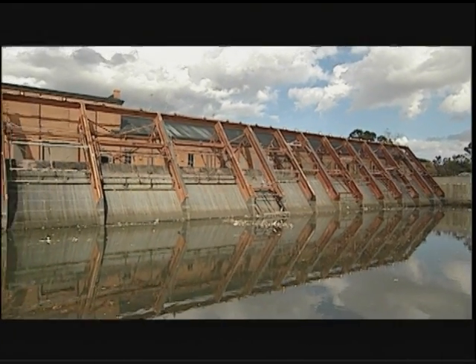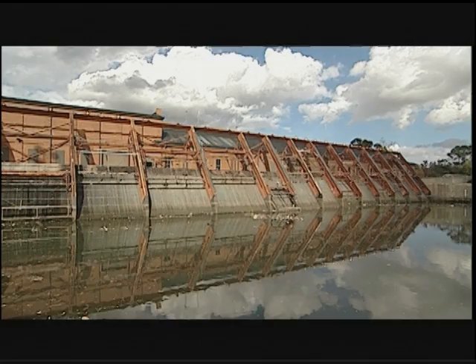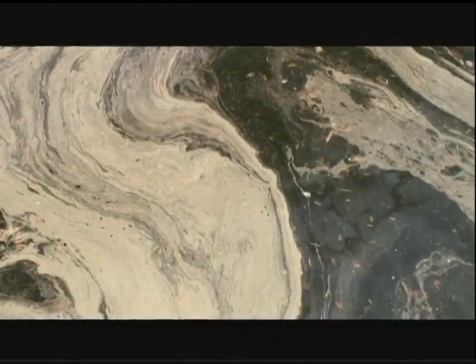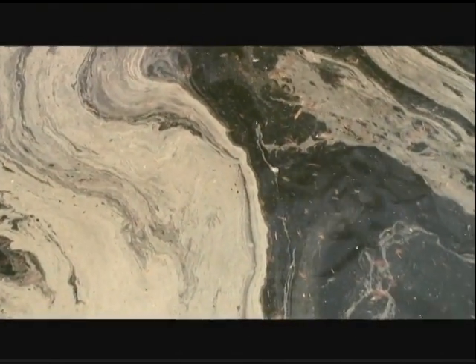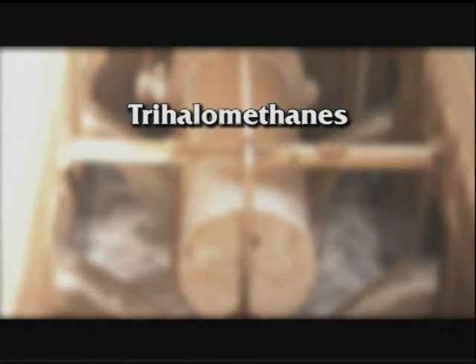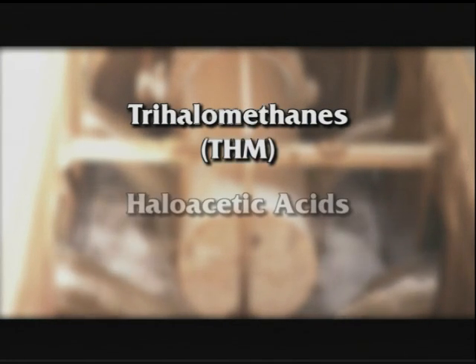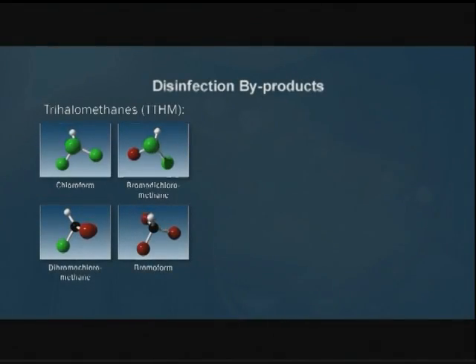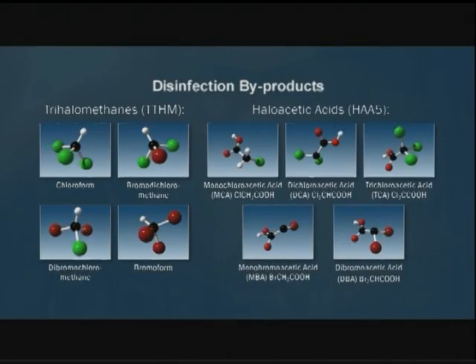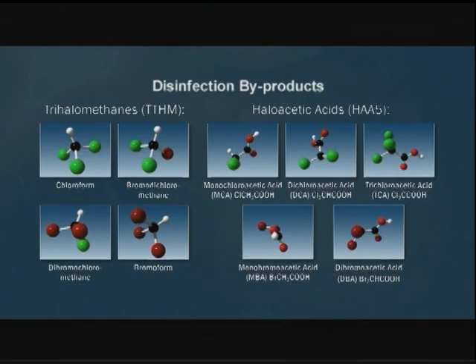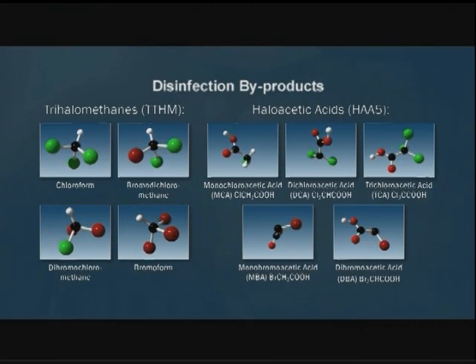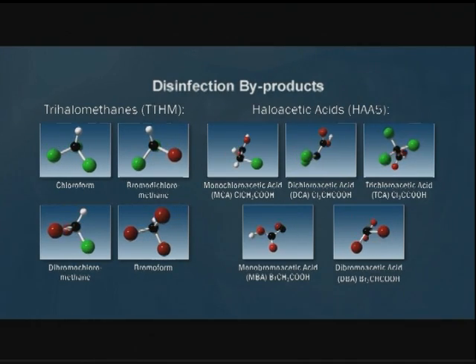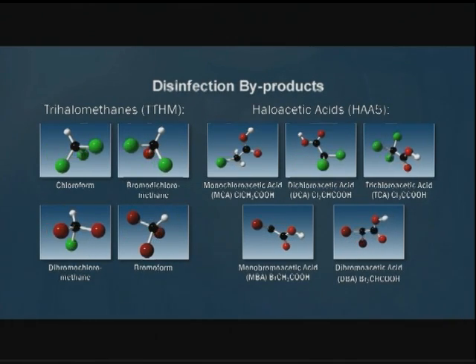It's important to remove organic materials from the source water prior to pre-chlorination because they can react with disinfectants to form DBPs. The two main groups of disinfection byproducts that are regulated are trihalomethanes, abbreviated THM, and haloacetic acids, or HAA. The four THMs and the five HAAs act as indicators for DBP occurrence in a water system. Therefore, the reduction of these two groups indicates a reduction in overall DBPs.